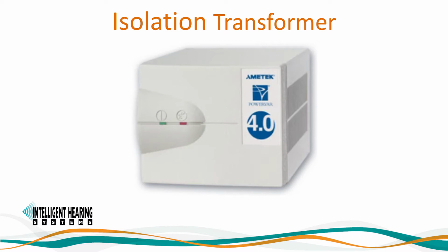Please note that duet devices do not require an isolation transformer unless it is being used in the OR or it is set up on a metal cart. If the isolation transformer is not earth-grounded, then you will create a floating ground, and it is then preferred that you bypass the isolation transformer and connect the device directly to an earth-grounded outlet. All components connected to the computer must be connected to the same ground.